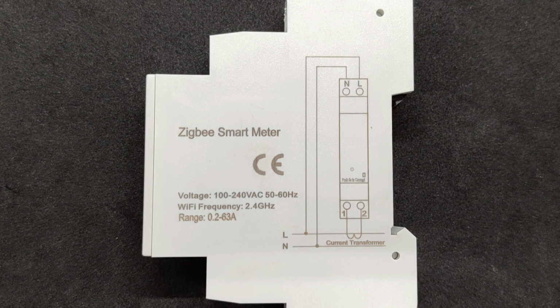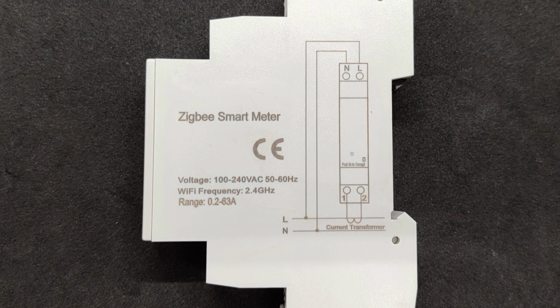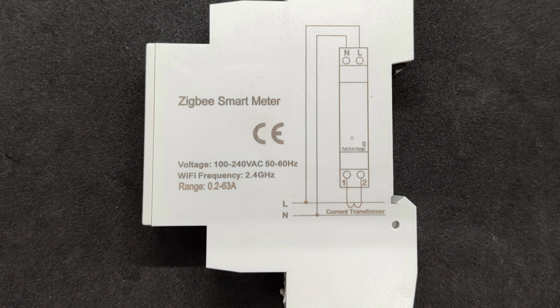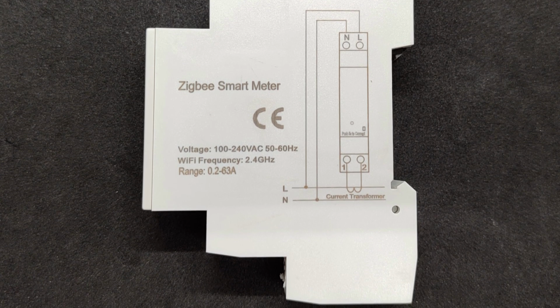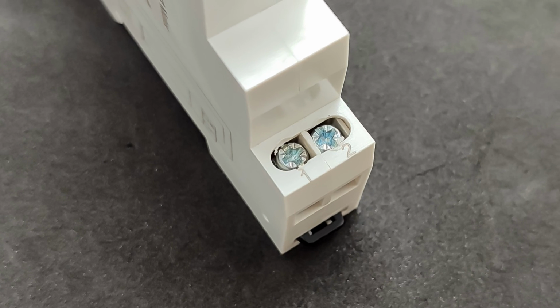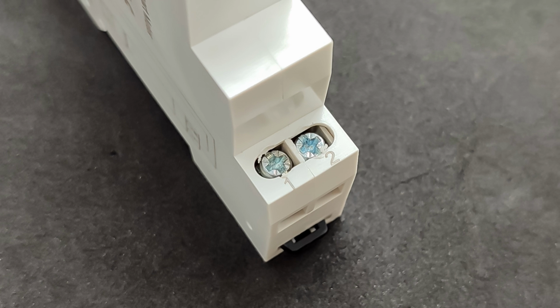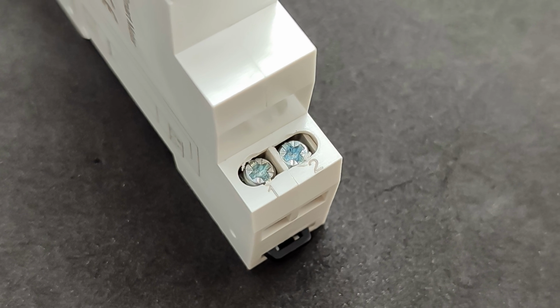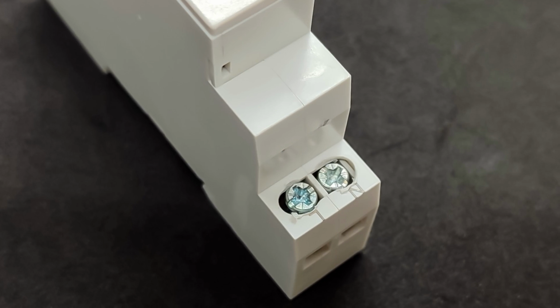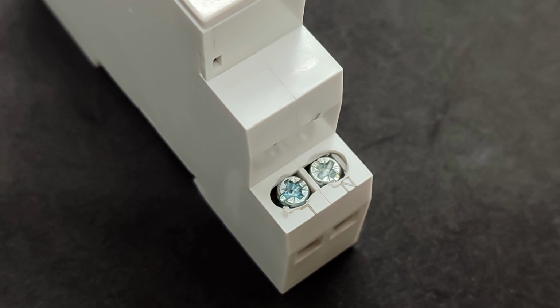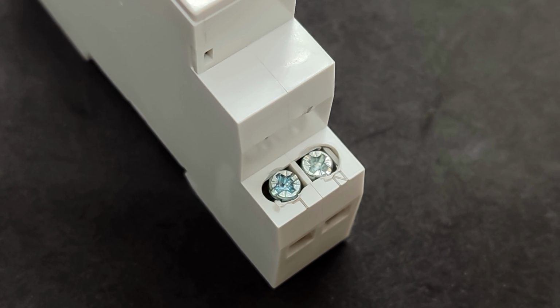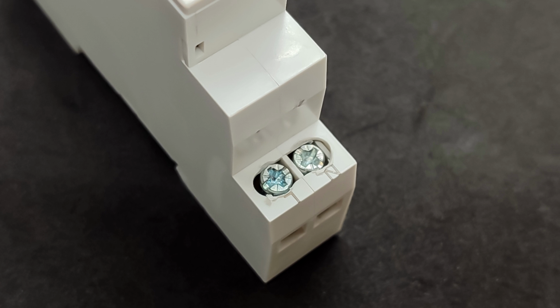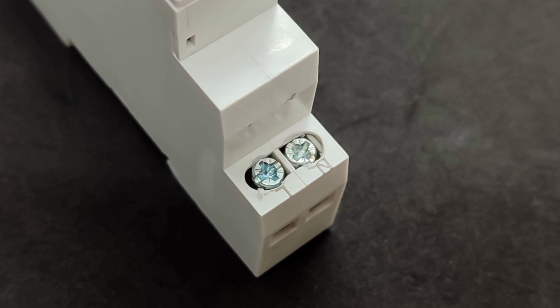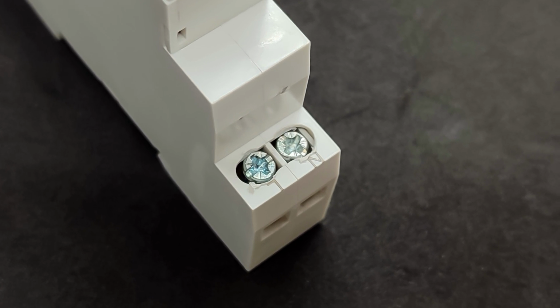On one side of the device, there is a wiring diagram. Power is supplied from the top, while the current transformer connects at the bottom. The contact pair for the transformer includes a black wire connected to terminal 1 and a red wire to terminal 2. The contacts for connecting the power line, phase, and neutral are required for the energy monitor to operate and to measure voltage. Thin wires can be used here since the load is minimal.